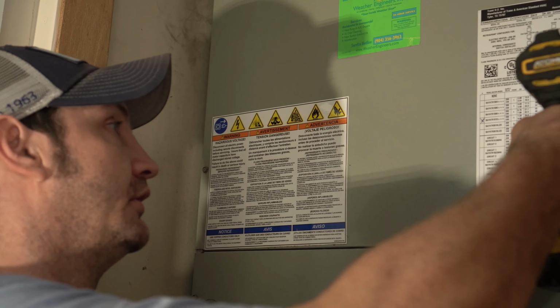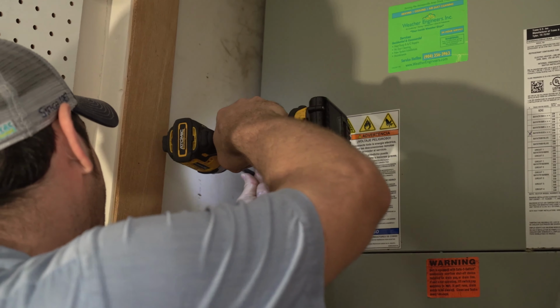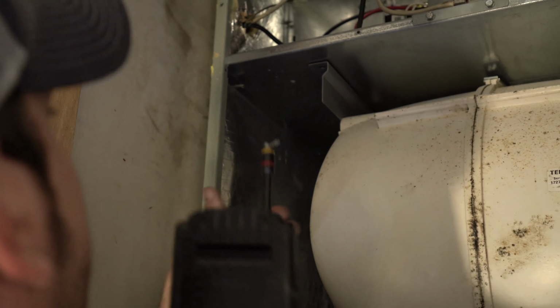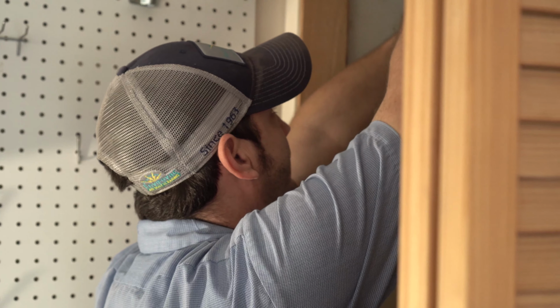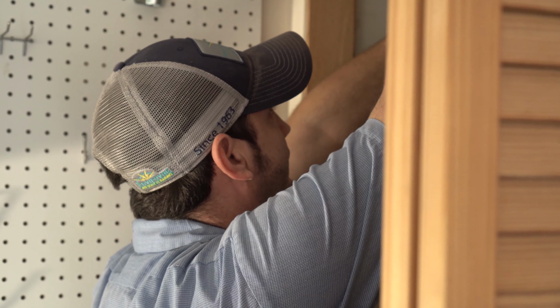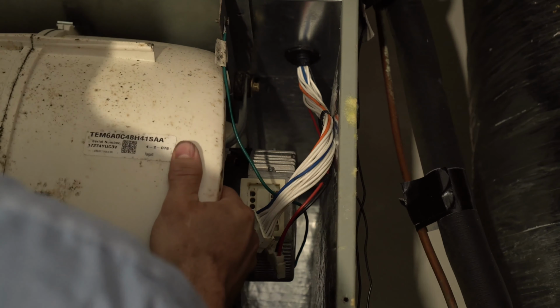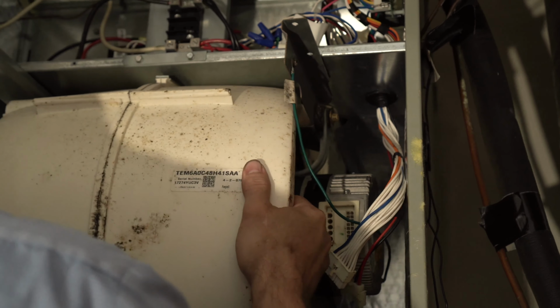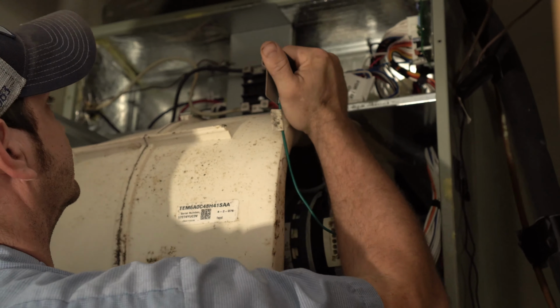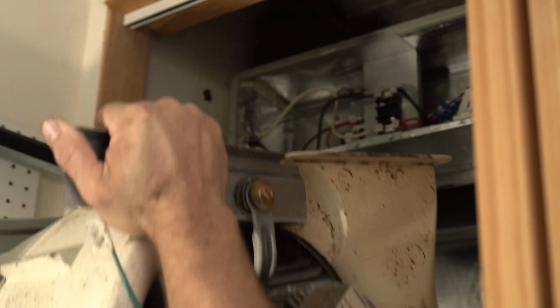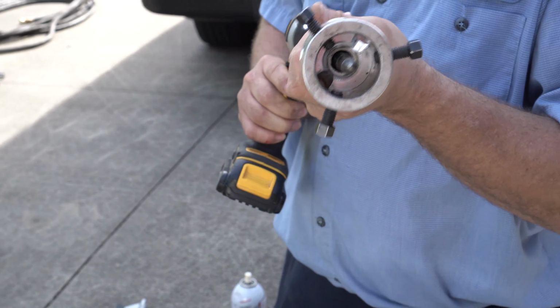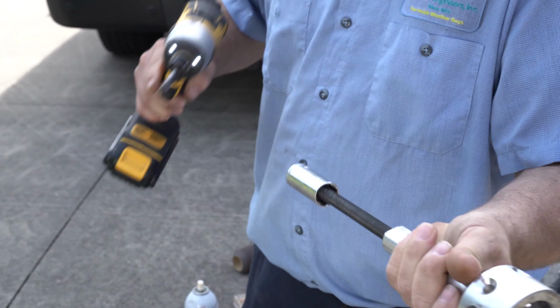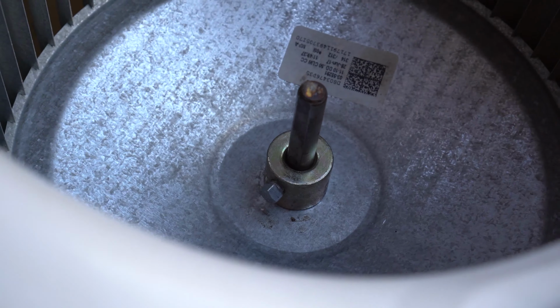Successful removal of the blower can be achieved by following these important steps. Step 1. Disconnect the blower from the power source and test it to ensure it is not active. Step 2. After removing the air handler access panels, mark the blower wiring for easy reassembly later on. Step 3. Disconnect the wiring, remove the blower assembly, and separate the wheel from the motor and the housing using a blower wheel puller. Step 4. Mark the wheel and rotation for reassembly later.